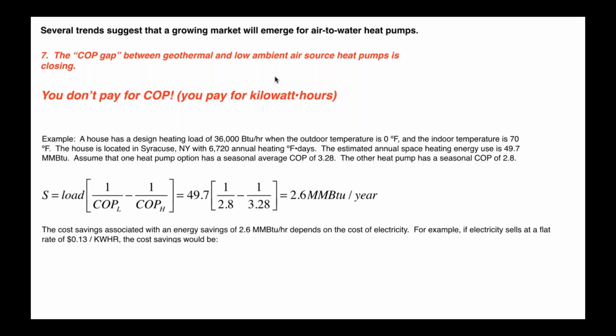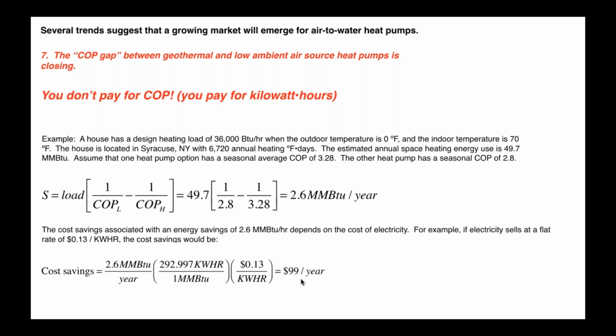I compared a geo with a seasonal heating COP of 3.28 to an air to water with a seasonal COP of 2.8. And it works out to be about, let's see, right around $100 a year, okay? So let's say a hypothetical, let's say it was an extra $10,000 to install that earth loop. You got back some of that, so let's say your net cost was $7,000 to install that earth loop. How are we going to amortize that extra $7,000 with a savings of $99 a year? You can't. The heat pump will be out of service by the time you're even approaching any kind of a payback on that. So keep that in mind.